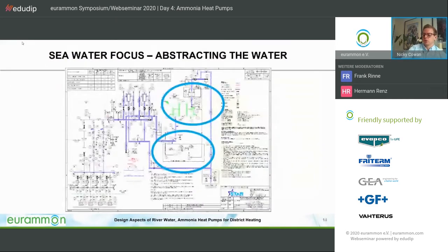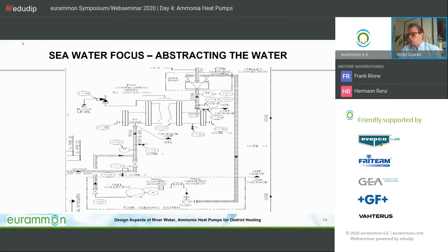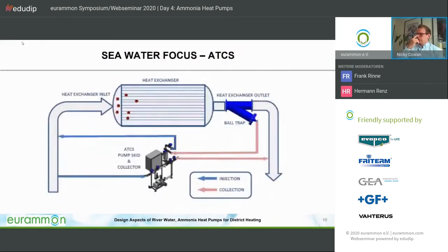After the mussel stops, because we've got the river water going straight into the heat pump evaporator, even though we've got the self-cleaning filters in the river, and an extra layer of filter stopping mussels coming in, we're super paranoid about having anything in the tubes that is going to be detrimental to the performance, and sediment and silt is always going to make its way in. We then have an automatic tube cleaning system, and it looks kind of like this.